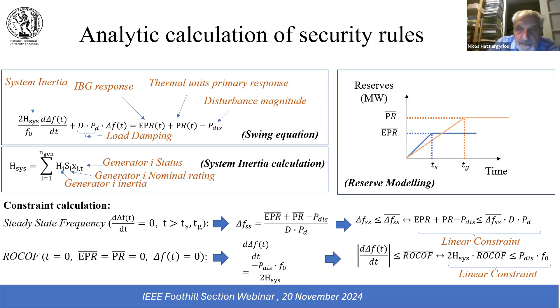This is a bit more difficult, but still possible: to calculate the frequency nadir. This is the time after the reaction of the power electronic units, while the thermal generators are still at an intermediate state, somewhere between TS and TG. There you can find the frequency nadir using this equation, which is of course nonlinear, but you can linearize it piecewise and use it again as constraints in your unit commitment problem. This requires a number of auxiliary binary variables, which makes the problem a bit more complicated, but it's still possible to linearize the security rules and use them as constraints in your unit commitment problem.